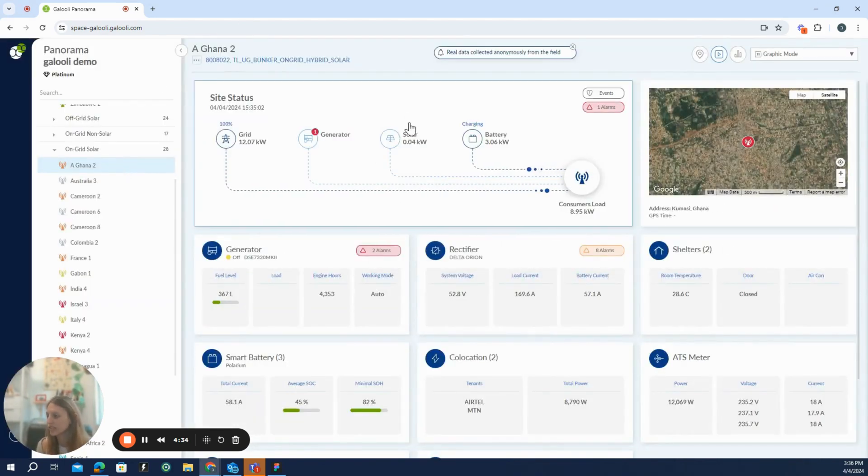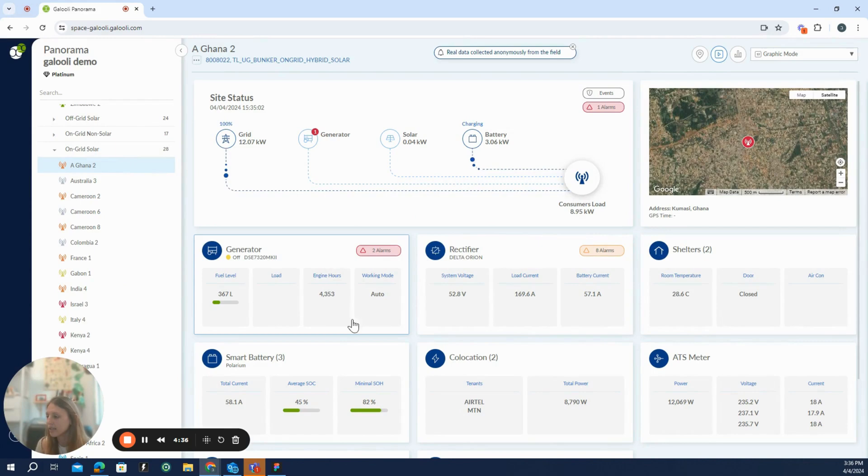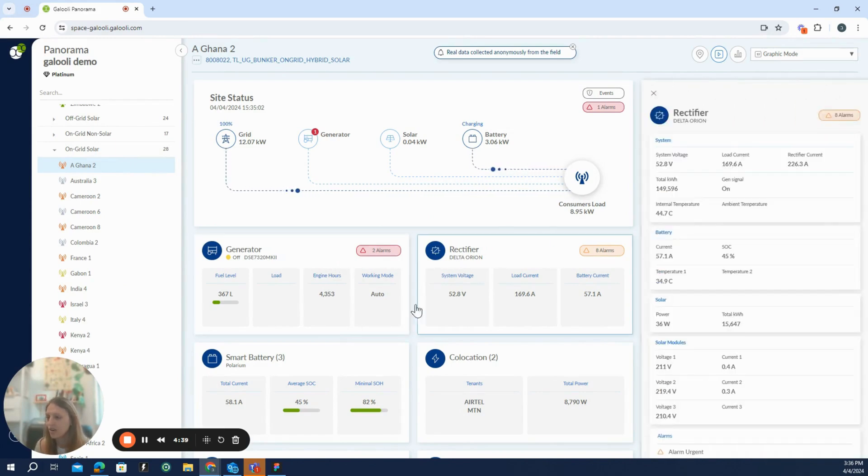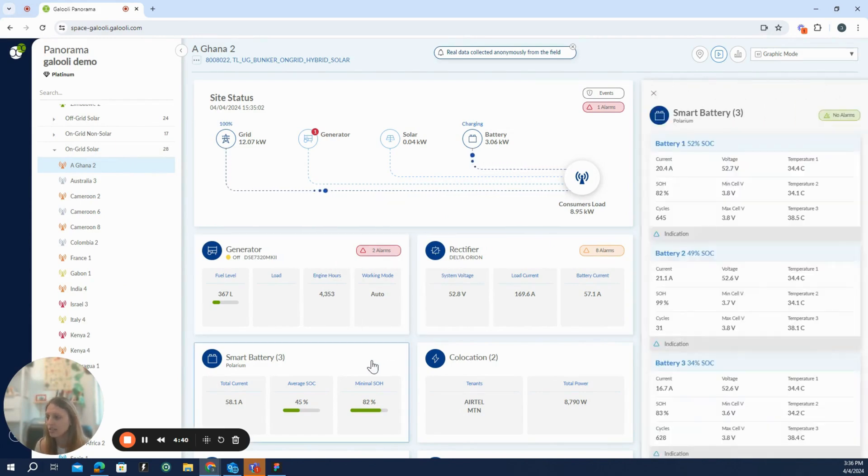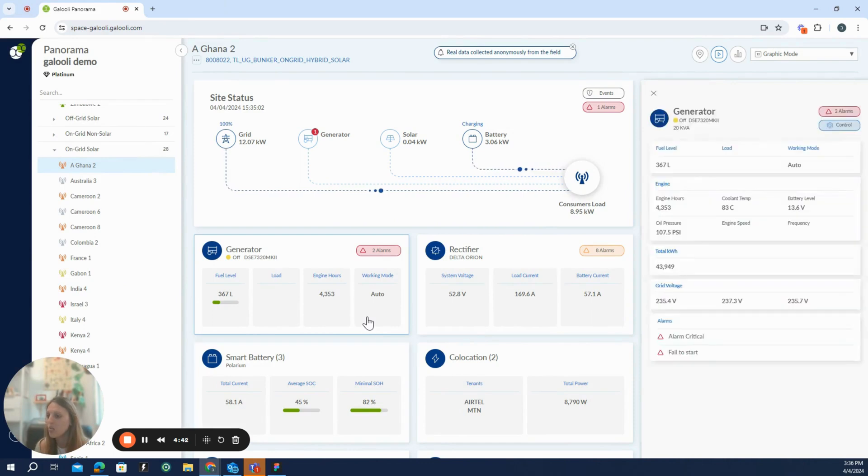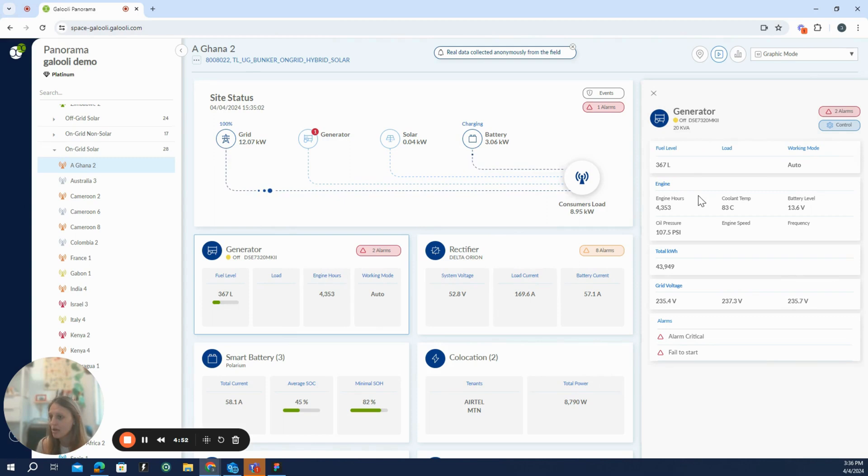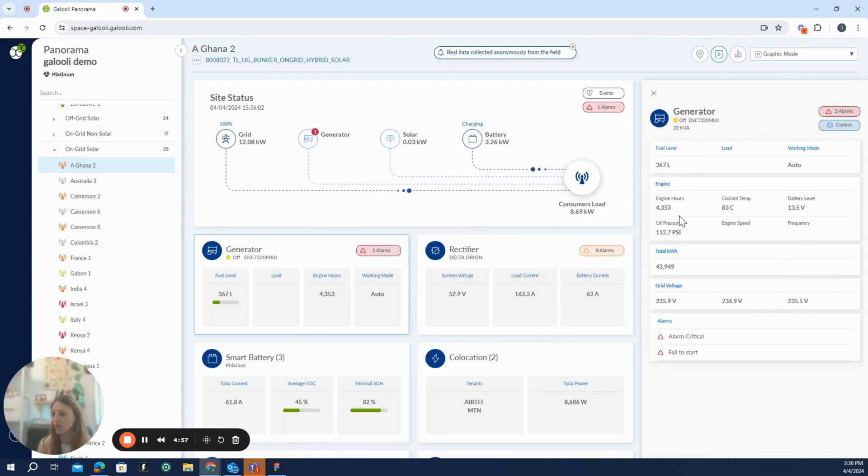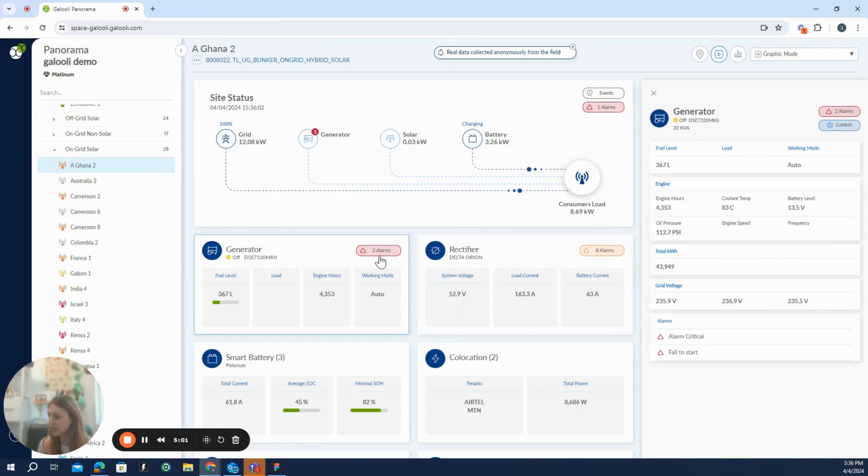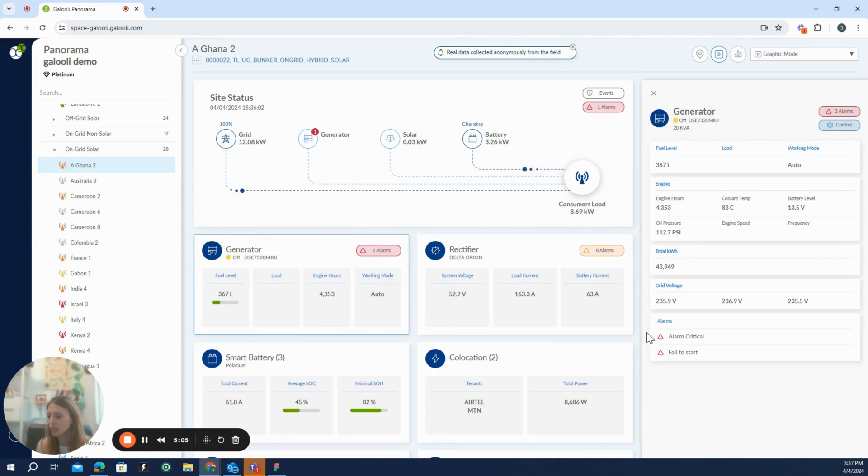Let's continue with the first site we saw. If I click any of the cards here, I will get a more detailed view into the situation of this specific asset. So we can see for this generator, not only the four parameters we have here, but also a closer look into the generator, coolant temperature, battery level, oil pressure, etc. And if it alarms, as you can see here, it states that the generator has two alarms. They would also be detailed inside the card.